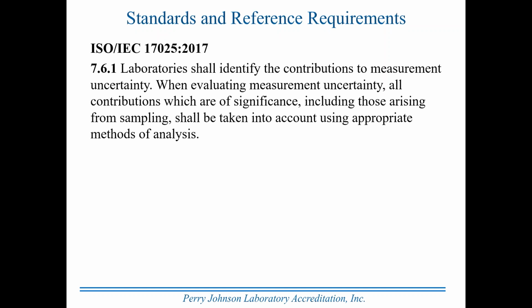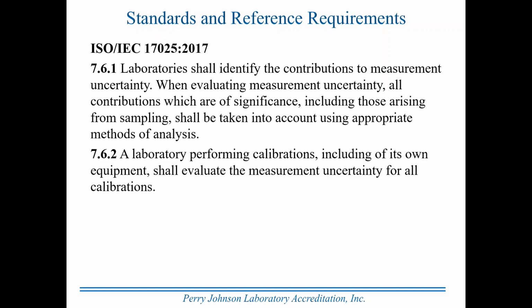7.6.1, we just read that, so we'll go on past that. But there's 3 in succession that you want to be familiar with coming out of the standard. 7.6.2, a laboratory performing calibrations, including of its own equipment, shall evaluate the measurement uncertainty for all calibrations. So this is speaking specifically to calibration laboratories that are calibrating equipment. Even if it's their own equipment, they still have to evaluate measurement uncertainty for all calibrations.